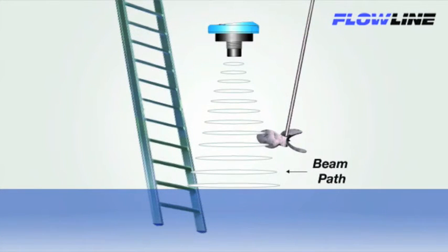But obstructions or obstacles do exist, and ultrasonic sensors should be located away from them whenever possible. Obstacles inside the beam path can disrupt the acoustic signal and be falsely detected as liquid level.